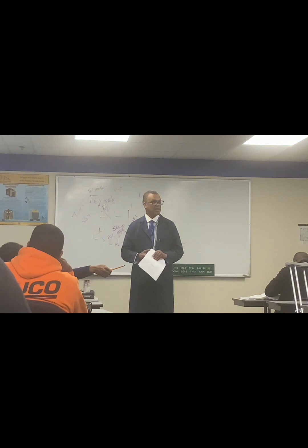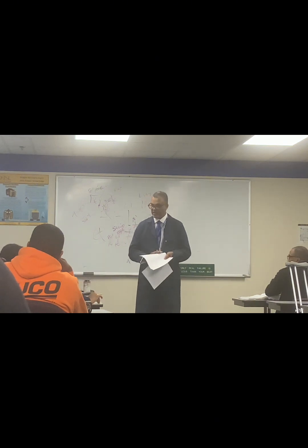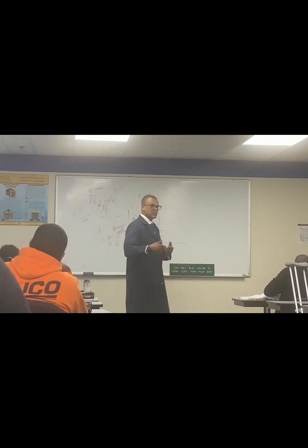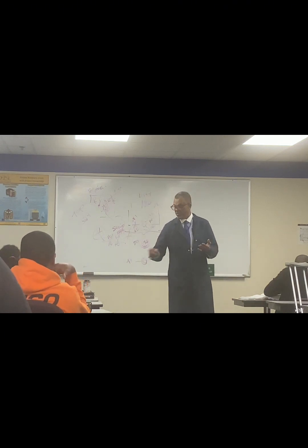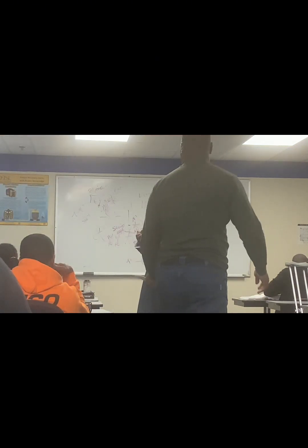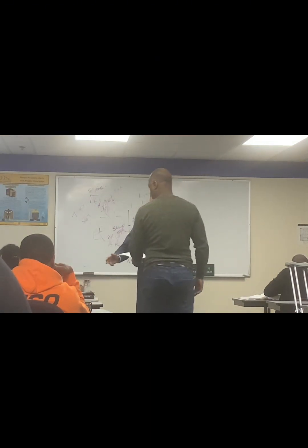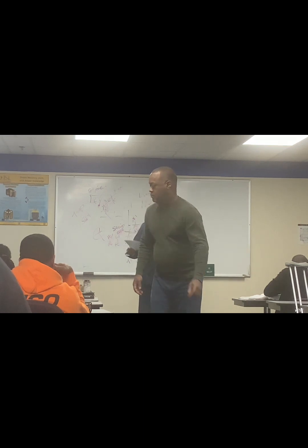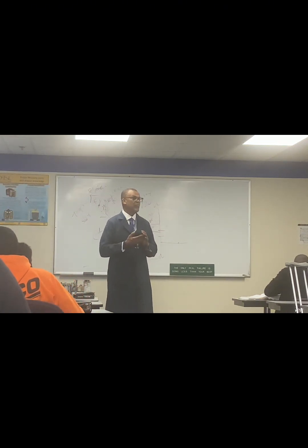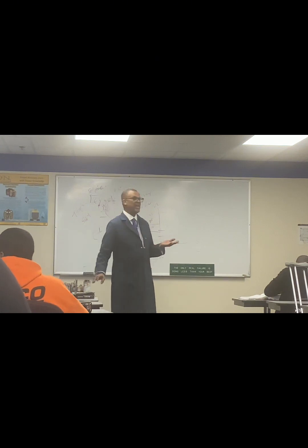Is there a limit to how many loads can be on the motor? The only thing that limits loads is the design of the system. When we design an electrical system, we determine by the loads that are rated in amps on each component, whether it's in a motor circuit, and then we design the wiring and the breaker for that load not to exceed. For example, a furnace is 15 amps.